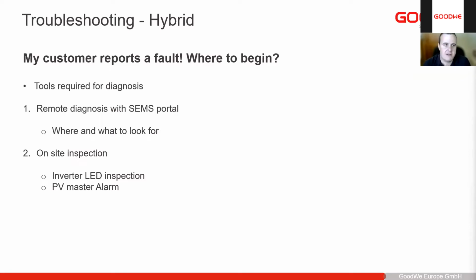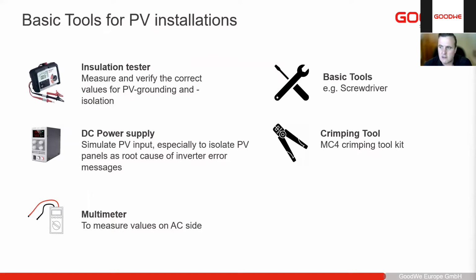So just to show a brief overview of tools that could be required for diagnosis. Remote diagnosis with the SEMS portal, where and what to look for. On-site inspection as well, inverter LED inspection, and PV master alarms. This is a brief basic view of the tools. An insulation resistance tester is most often used if there is a DC string fault and is a good piece of equipment to have when you are installing PV. A DC power supply with the hybrids is not really needed so much. And then your general tools, multimeter, and such.